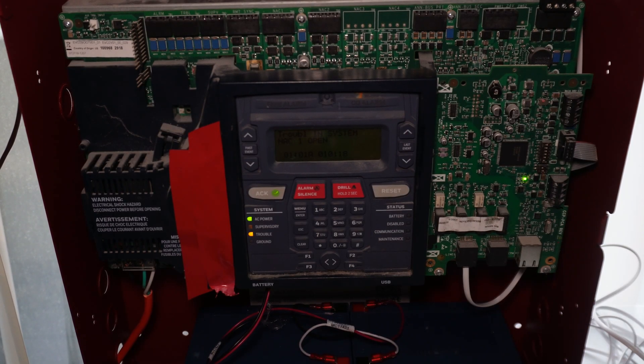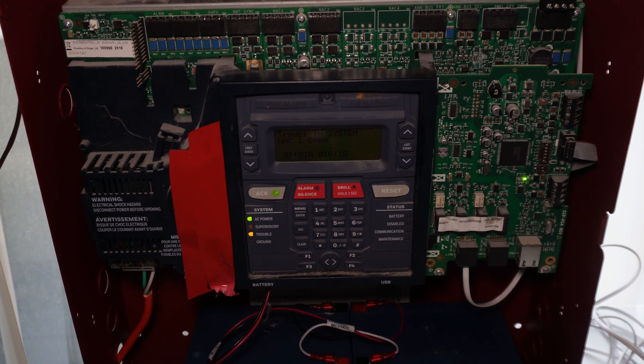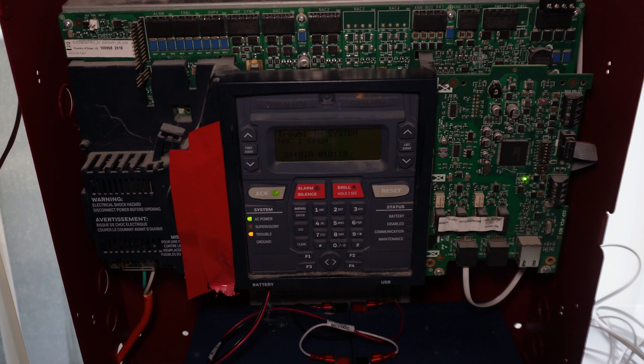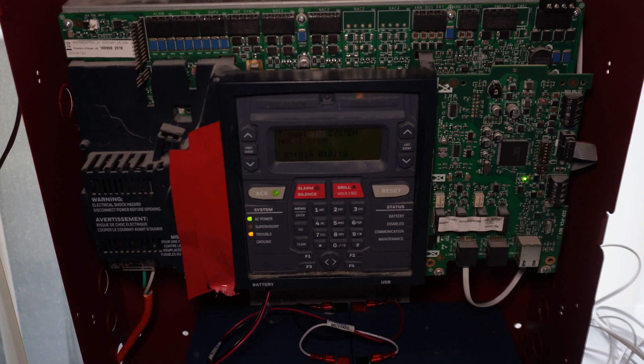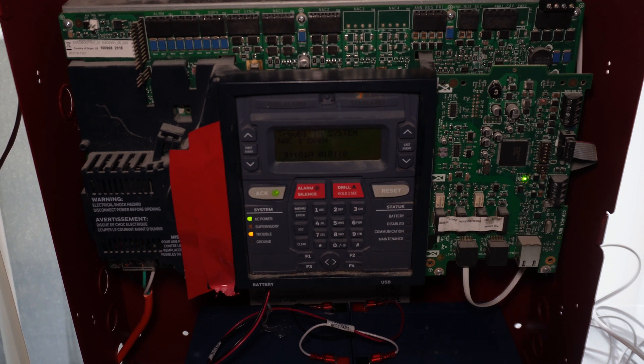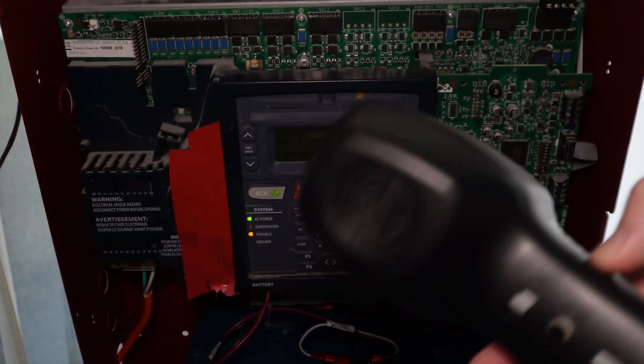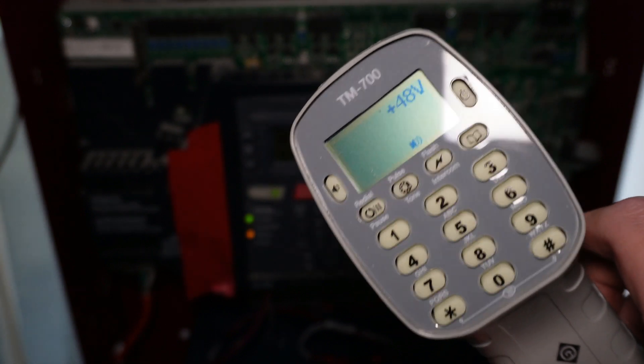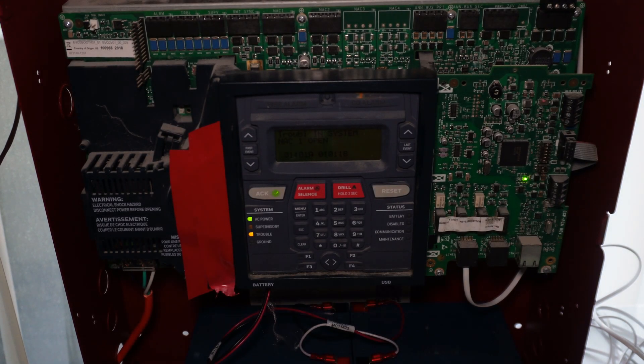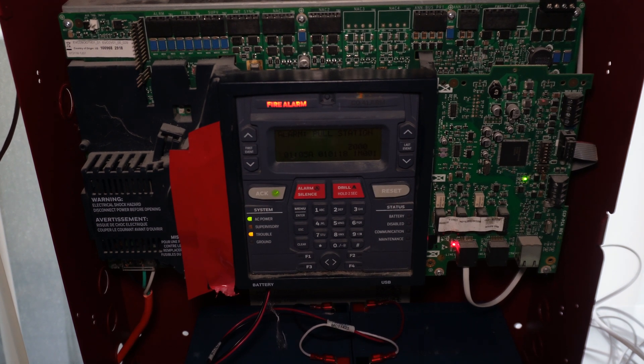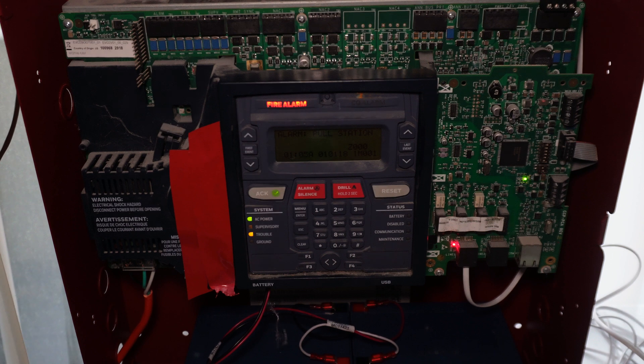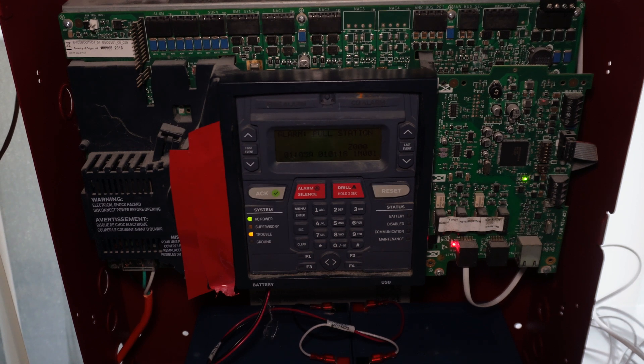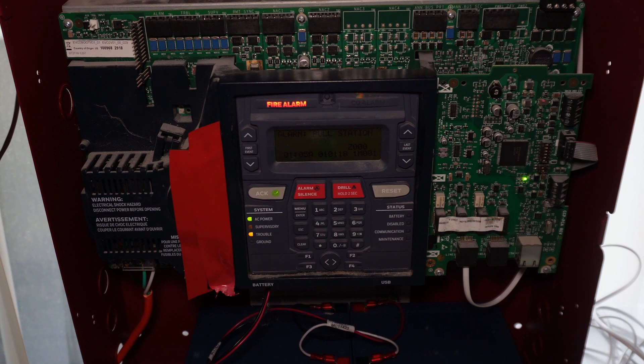Alright, so now that we have enabled the communicator to work and seem to have put in the correct settings for reporting, we are going to do an operational test. So for example, I'm going to set off an alarm and we're going to make a report. And I also have my telephone test set here connected to the same line. So we're going to listen to the conversation between the panel and the central station receiver.